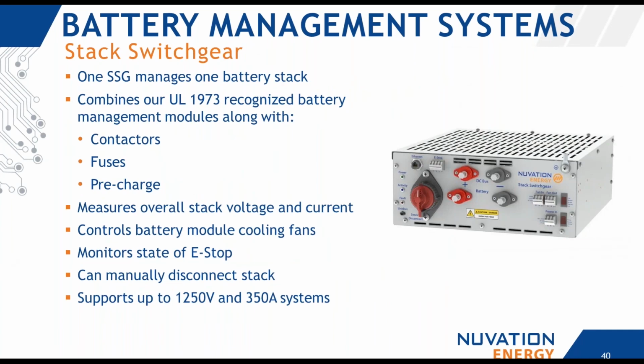As far as our stack switchgear goes, this is the next level up. So there's 1 per battery stack, and it's going to be combining our UL 1973 battery management modules with additional contactors and fuses. There's a pre-charge circuit inside. And again, we're in the process of getting this all UL recognized at the stack switchgear level.